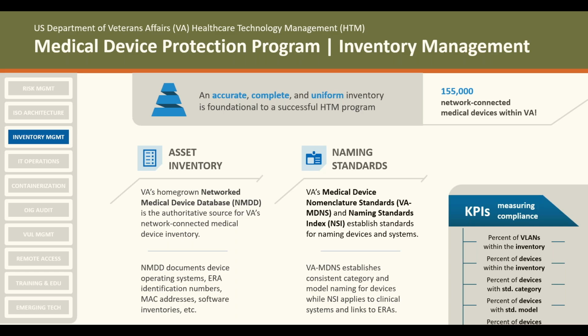So we measure this using key performance indicators. We're taking a look at your scanning in NMDD and seeing what percentage of your VLANs are properly captured within your NMDD inventory. What percentage of devices are in there? What percentage of devices are matching the standard categories and standard models, and what percentage of the devices have sufficient data fields filled out? We have many network tools that allow us to identify where there are gaps on the network. With tools like SMAC and Splunk, we can see, hey, a device popped up on the network in this VLAN and it hasn't been filled out and completed in here. With SMAC, we're actually able to accurately pull in some of that data and fill it out, and then just go in and do a quick compliance conformance verification check. It's accurate, up to date, good to go.